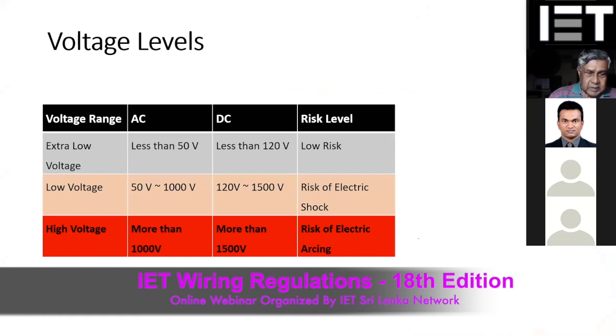Now, as I said, the main criterion for selection is the voltage level, because the BS7671 gives the rules and regulations to reduce the risk of electrical hazards. As per the IEC and the BS7671, there are 3 levels of voltages defined. There are subcategories as well. Those are the extra low voltages, the low voltages and the high voltages. The lowest one is the extra low voltage, where the voltage is less than 50 volts AC or 120 volts DC. Here the risk is minimal, so the risk of electric shock is very minimal if you are exposed to this type of voltage. That's why they are considered extra low voltage.